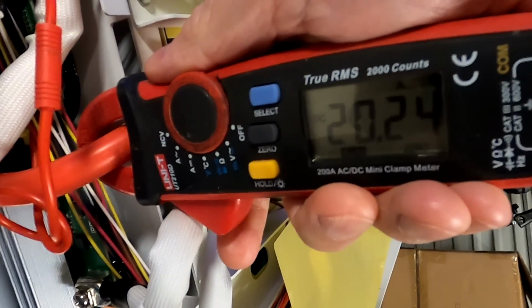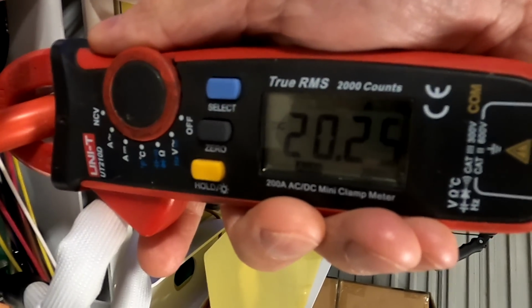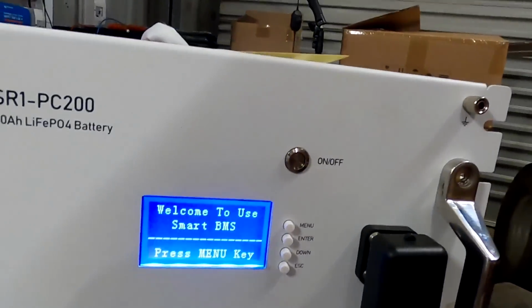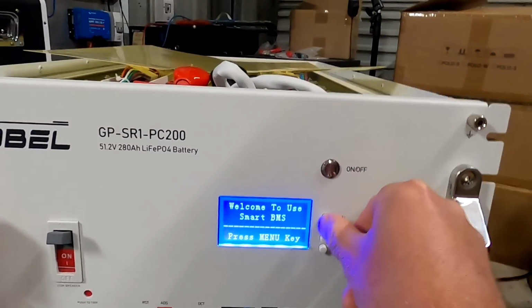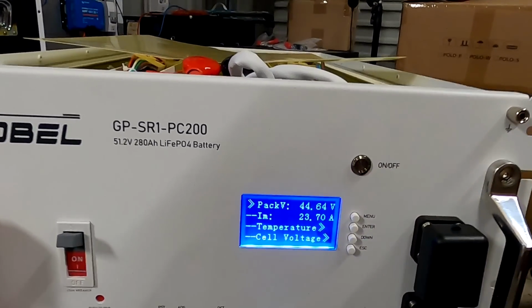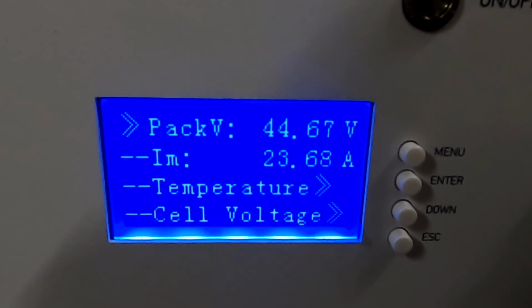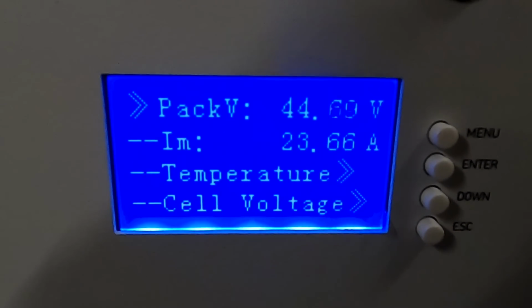Yeah, it's down to a 20 amp current limiter. So it must have exceeded the 150 amps actually to charge the battery, and now it's limiting to 20 amps only. Fully charged, fully discharged battery in parallel and nothing happens. So we're charging with 23 amps only. Otherwise you could have charge currents of several hundred amps.